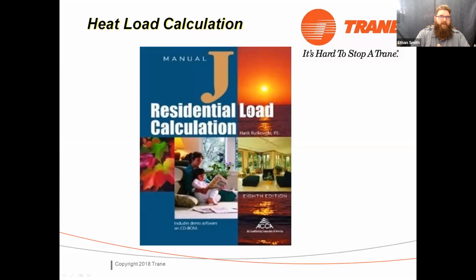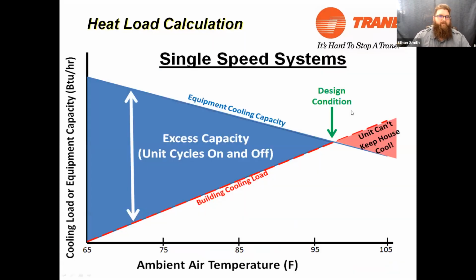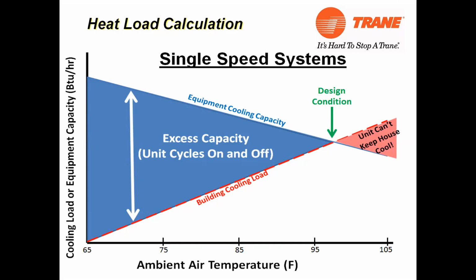So why is Manual J so important, guys? Correct size equipment for the home. Correctly sized equipment. When we say we're sizing equipment properly, we're sizing equipment to what's called a design condition over here in the green. That is the point at which our building cooling load lines up with our equipment cooling capacity. We can see that as the outdoor ambient temperature goes up, my capacity obviously goes down on my outdoor equipment, and my load goes up. So the point at which they cross is what we call our design condition. Depending on where you are, there are different design conditions based on your local climate.